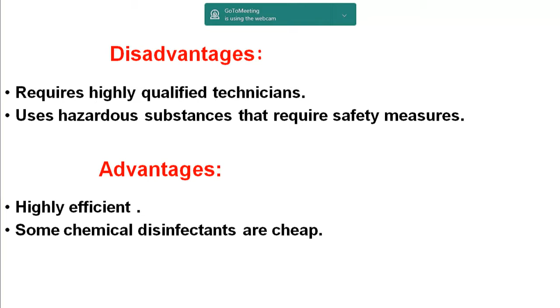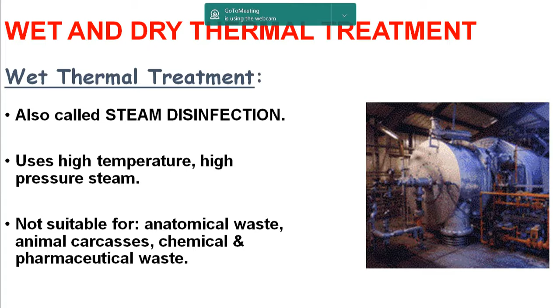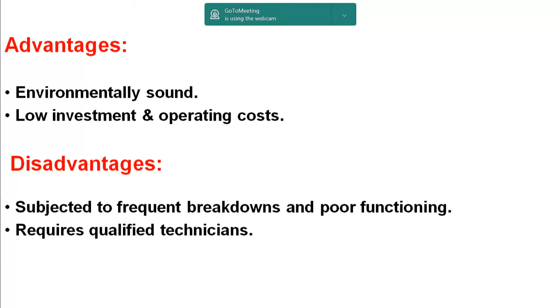Wet and dry thermal treatment. Wet thermal treatment, also called steam disinfection, uses high temperature, high pressure steam. It is not suitable for anatomical waste, animal carcasses, chemical and pharmaceutical waste. Advantages of the wet one: environmentally sound, low investment and operating cost. Disadvantages: subject to frequent breakdowns and poor functioning, and it requires qualified technicians.